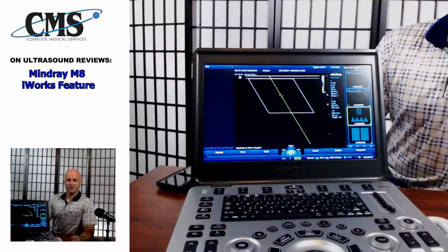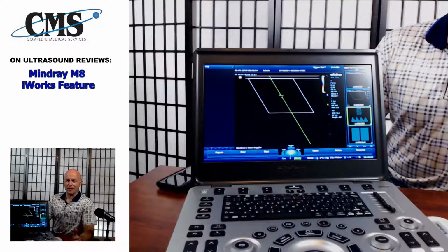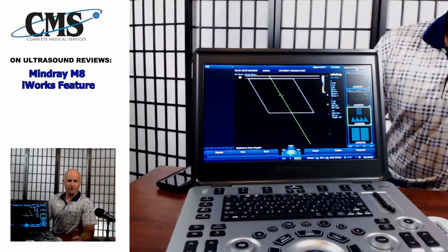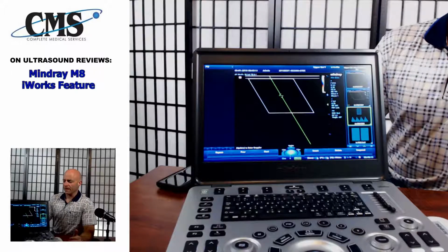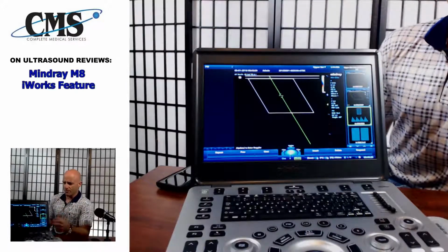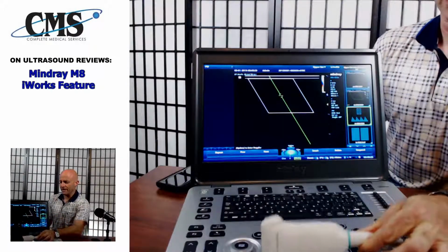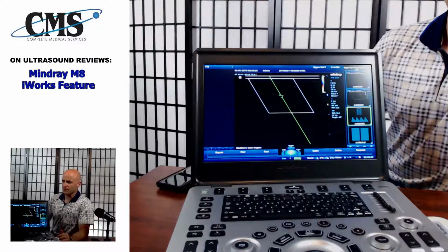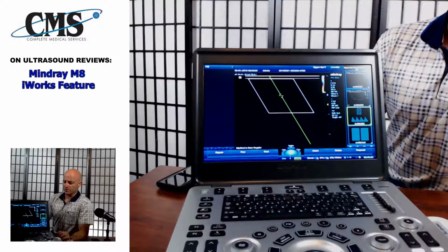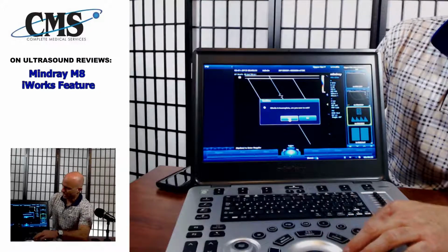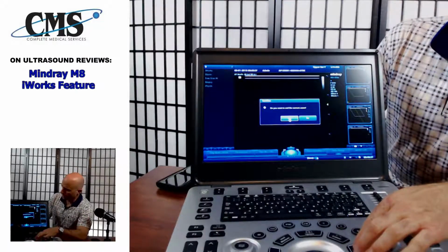Today we're going to be discussing the iWorks feature for the Mindray M8. The iWorks feature is an automated workflow feature for different protocols depending on the specialty that you've selected with your given transducer. Today we have the linear transducer connected, so any of the presets are going to be related to the linear transducer.